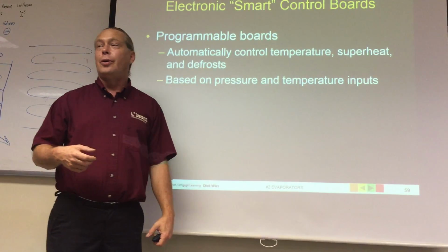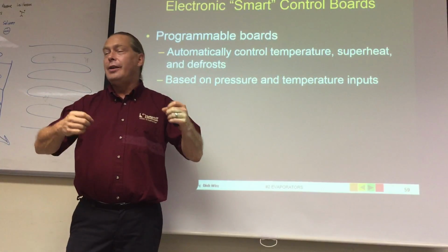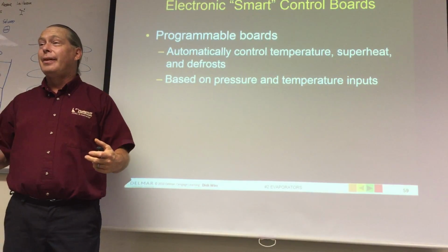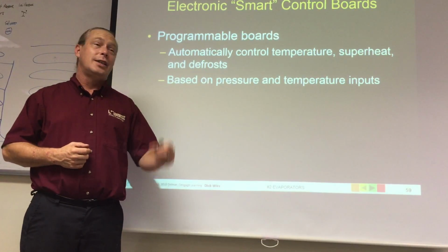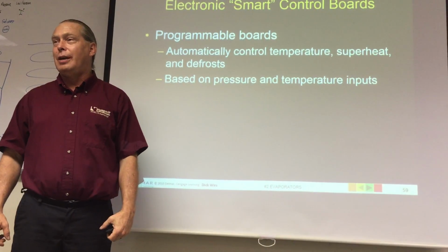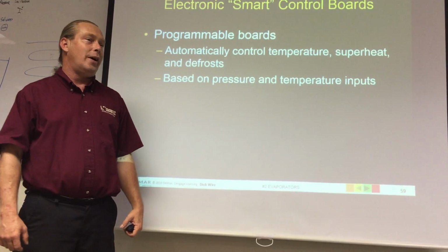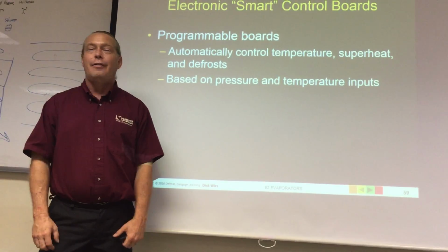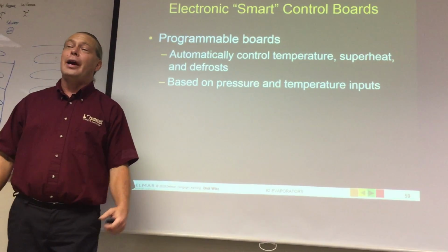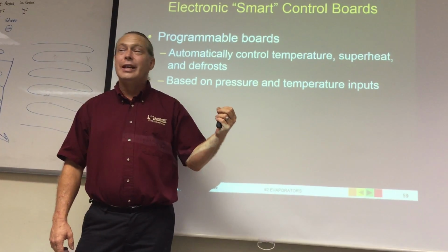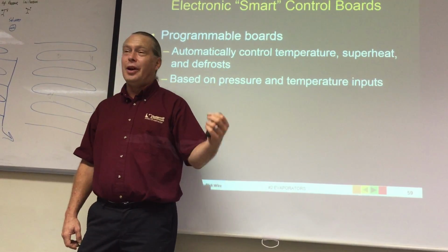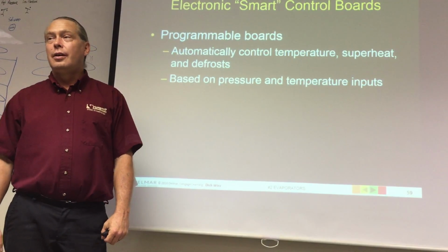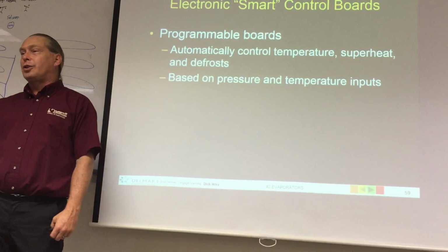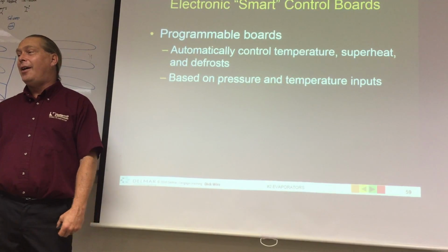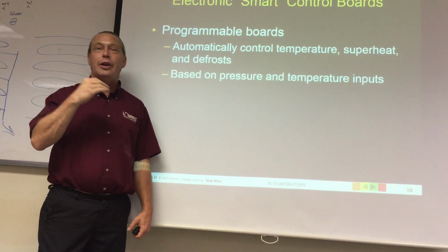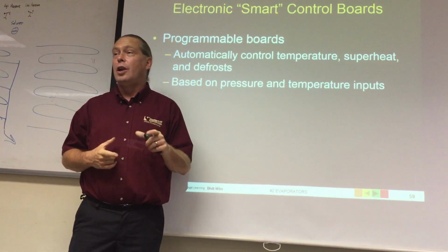And it can also be controlled and told, you are in defrost from this time to this time. And it's gonna monitor that defrost, and it already has a transducer on the coil temperature. It's gonna be the one that says, hey, I think the coil's warm enough. Let's turn the air conditioning back on. And by the way, I've got control of the relay that runs the fan too. So when it gets cold enough, I'm gonna close that switch. So in a way, all those complex controls that we're learning now, because you need to know them, are starting to get more and more replaced by a central logic board.